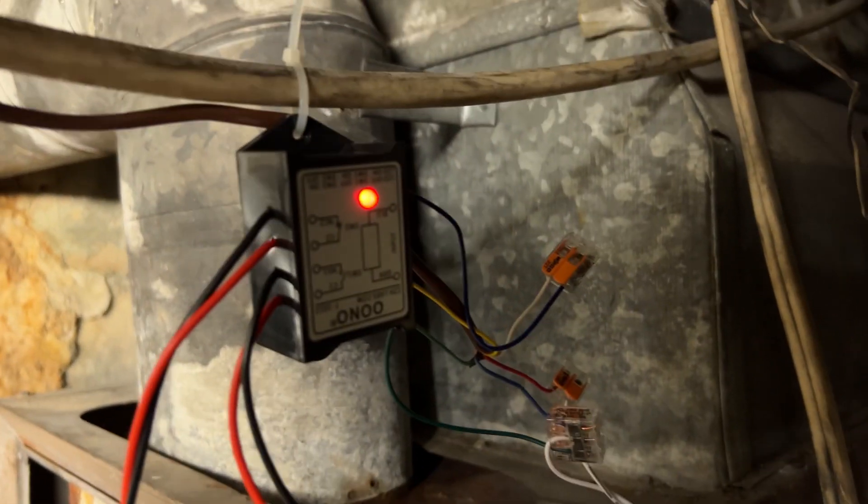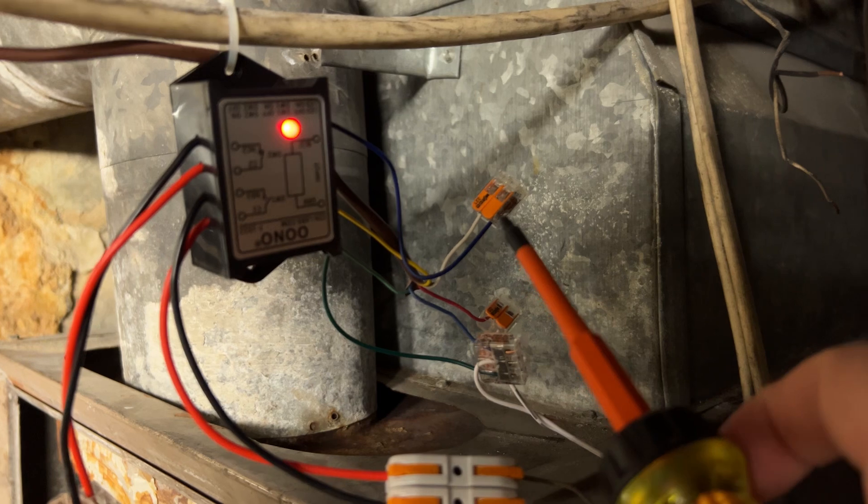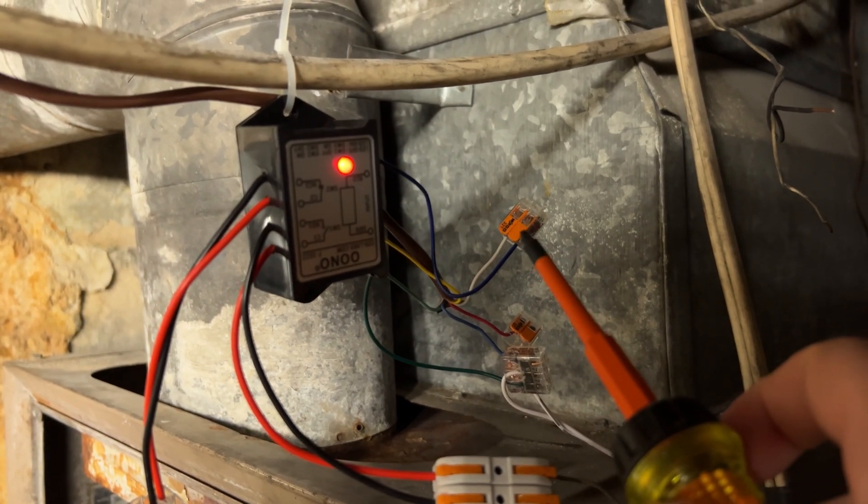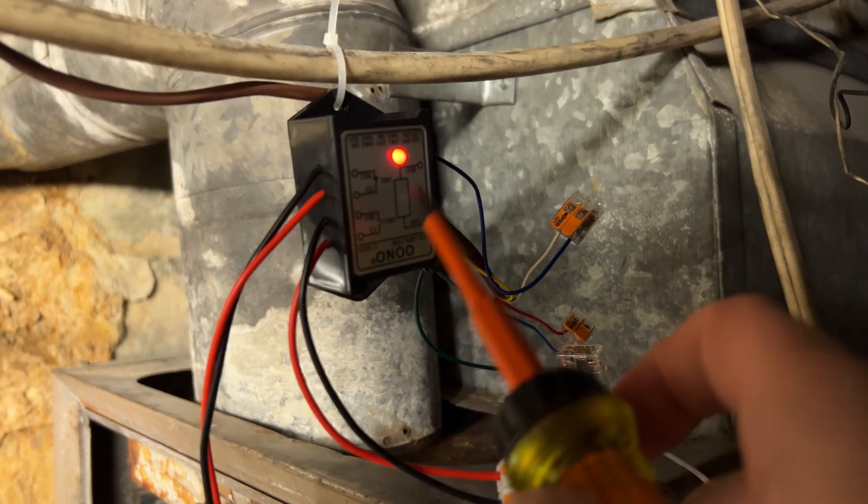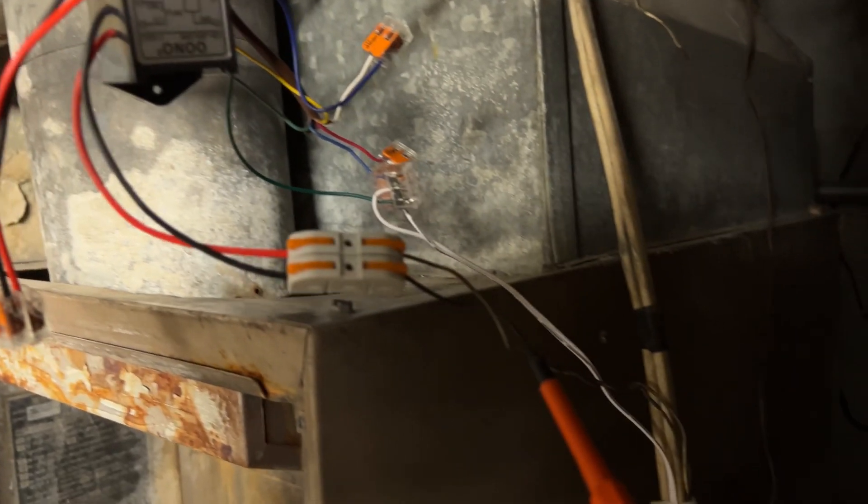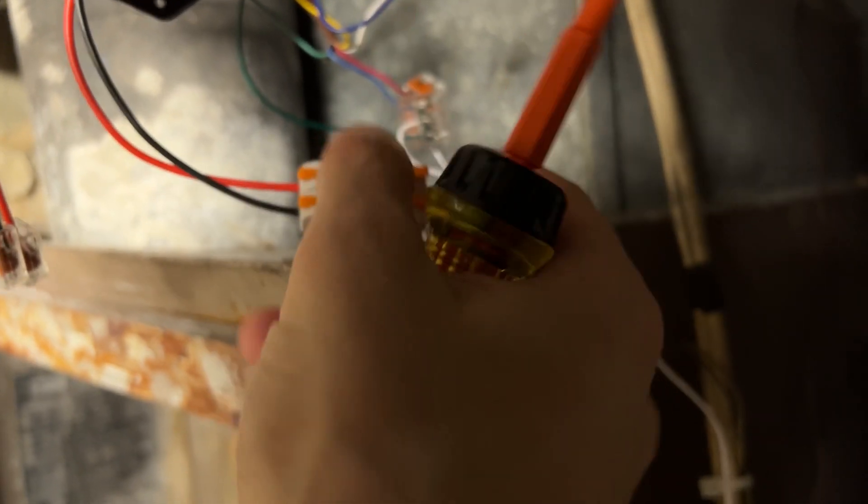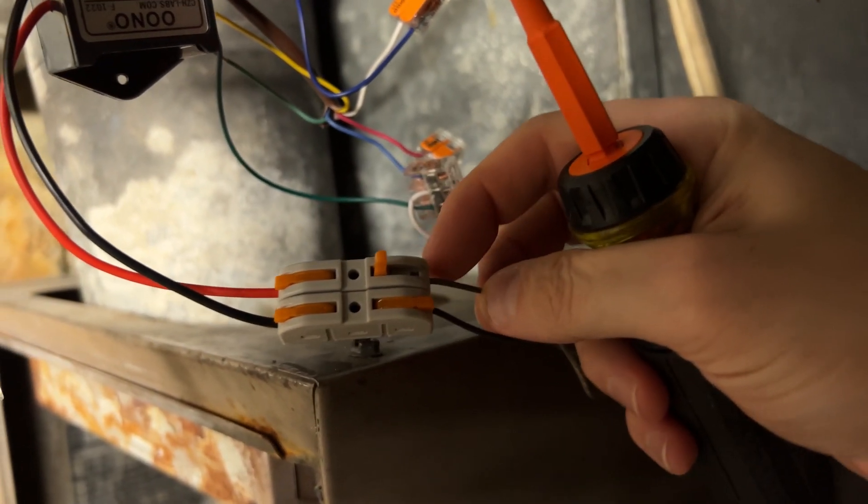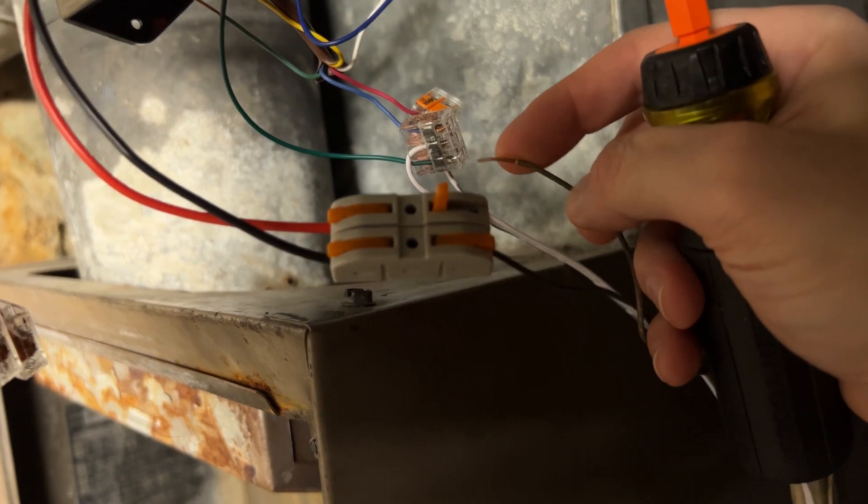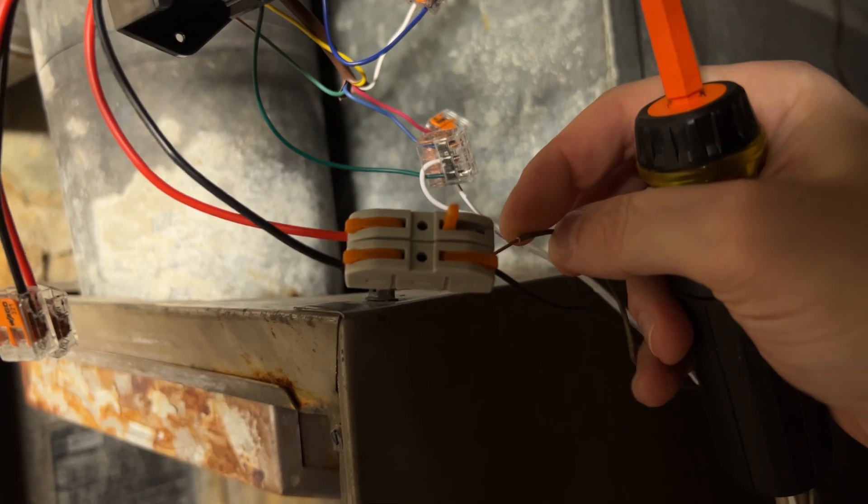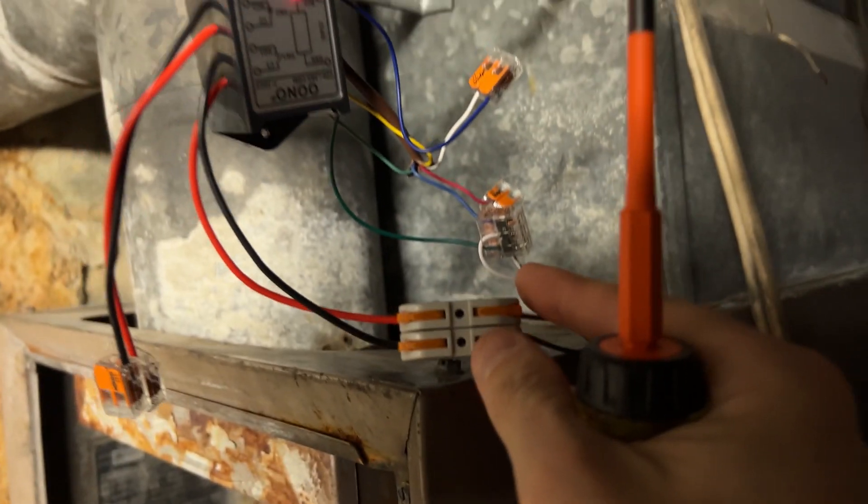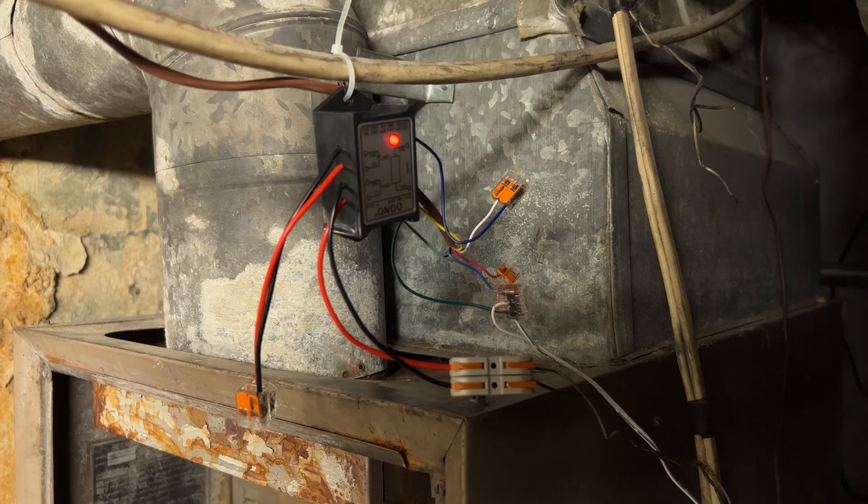All right, so we're back at the furnace. The Ecobee is on and you can see the relay is energized. So all that means is that that white wire is energized. And because we have 24 volts here and we have our common here, that's kicking our relay on, which is in turn closing the switch, which is putting our furnace on. And in fact, if I just take this from this side as kind of an experiment, take this out. So here's our white wire from our furnace. If I disconnect that, obviously you can see the furnace goes off. So even though the relay is on now, the furnace is off. And then if we connect this back up again, our furnace goes back on.